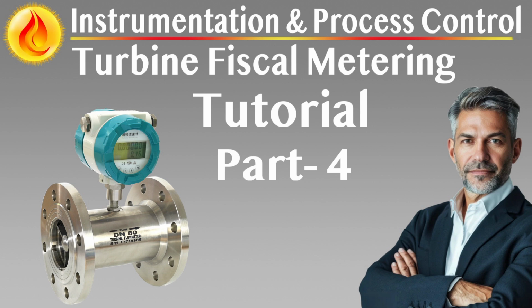The prover microcomputer must support direct printing of validation reports, including meter ID, date, time, flow conditions, K-factor results, number of runs, deviation spread, and any annotations related to abnormal conditions. This reporting capability ensures transparent traceability and supports compliance with fiscal metrology standards. Overall, the prover microcomputer must deliver high accuracy calibration, system-level coordination, and rigorous documentation, enabling the metering system to maintain traceable accuracy across operational cycles and over time.